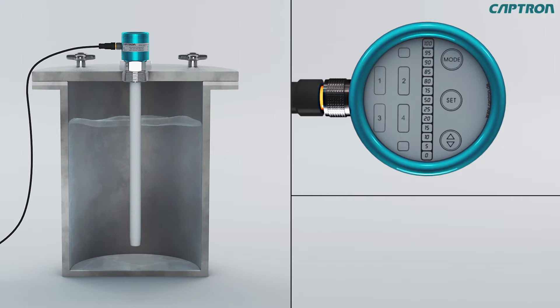The probe then jumps to the next step, setting the switch point SP1. The now blinking green LED shows the last set value. You can change this with up-down. When the switch output function is set on NO, the output is on high as soon as the switch point is exceeded.